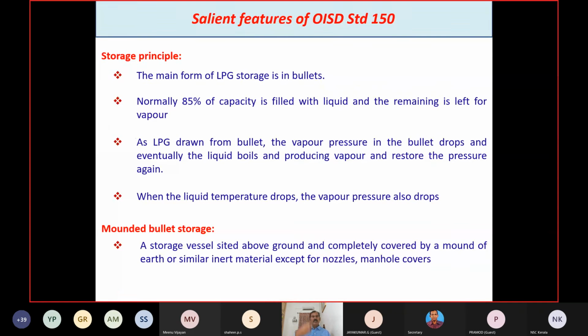The storage principle: the main form of LPG storage is in bullets only. The LPG is stored in bullets under pressure, and both liquid and vapor will be in equilibrium. Normally 80% of capacity is filled with liquid and the remaining is left for vapor, because the coefficient of expansion of LPG is very high. So some space should be left for expansion.